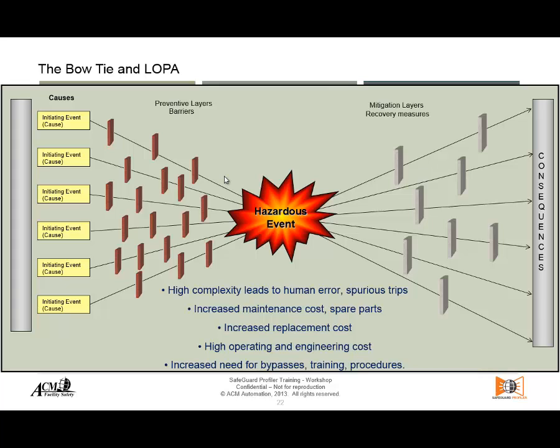On the left-hand side of your bow tie will be the preventive layers — trying to prevent that hazardous or unwanted event from happening. On the right-hand side you have the mitigation layers or recovery measures, meaning after you've had the unwanted event. I need to cope with those situations and stop the sequence of events so the worst credible consequence doesn't come to pass — stopping that mechanism before it reaches the target.